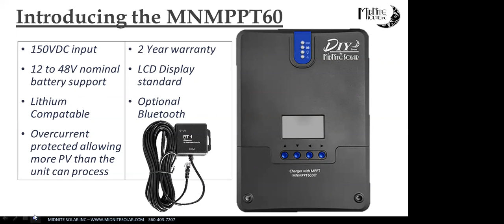So we're going to talk a little about voltage real quickly, and then we'll go back into some other stuff here. But the max VOC of your module is what you're really watching for here. And something to be aware of is sometimes you'll hear something like, this is a 200 volt charge controller. But if you read into the print and into the data sheet on it, you'll find out that it stops at 187 volts, not 200, for example. So you have to be real conscious of your product and what it actually does.